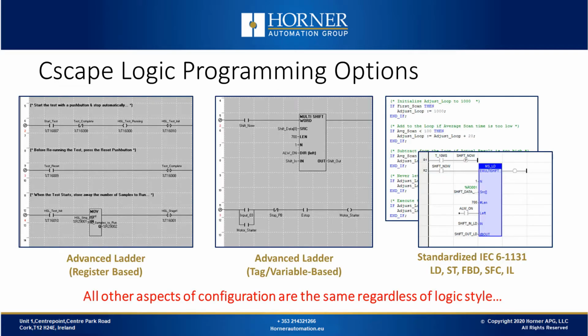You have multiple options for what form of logic programming you want to do. You can choose between register-based advanced ladder, variable-based advanced ladder, and IEC languages. With register-based advanced ladder, you need to map your variables to specific memory locations in the controller. With variable-based advanced ladder, most of the variables you create do not need to be mapped to specific memory locations. Exceptions to that include real-world I/O and some communications type variables that might be mapped to Modbus or something.